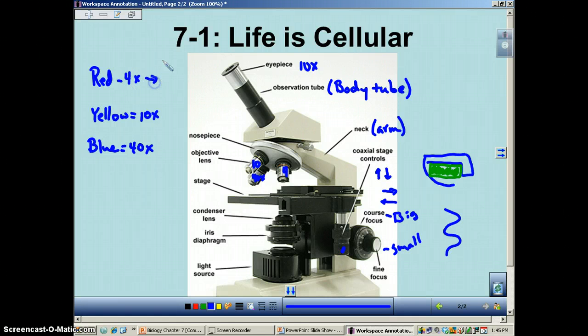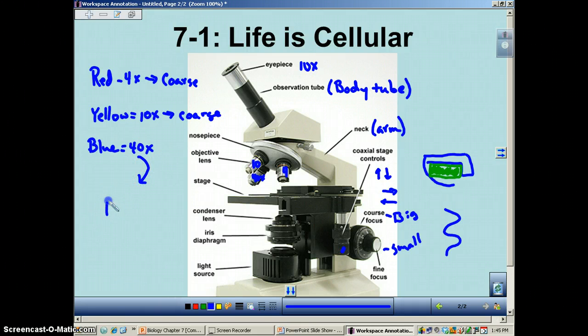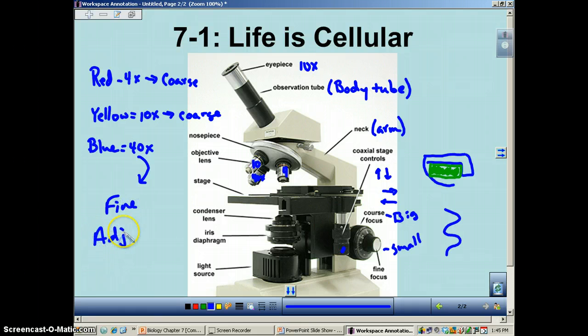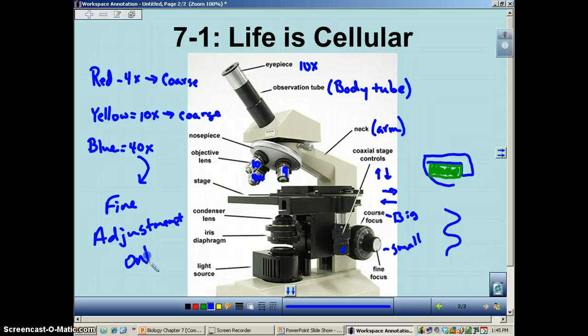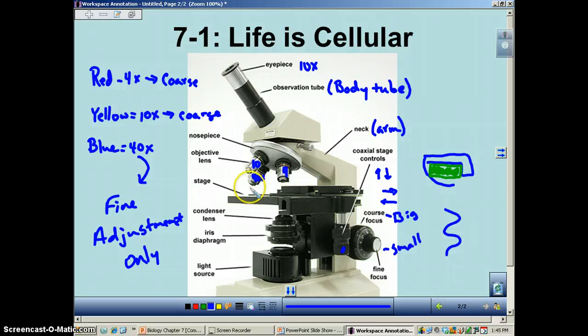For low power, you can use the coarse adjustment. Same for medium power — use the coarse adjustment. When you use high power, fine adjustment only. The reason is you don't want to use the coarse adjustment because you're going to move the stage so much that you'll possibly smash the slide right into the tip of the lens, breaking the slide and maybe damaging the lens.